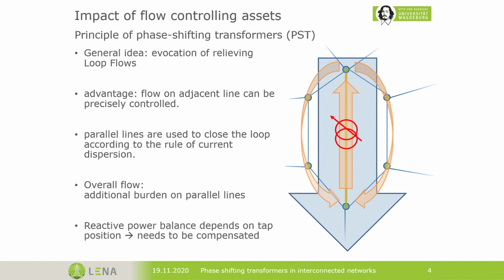All of these lines are therefore utilized from north to south direction. Let's imagine the line in the central part of this picture is overloaded. Then we want to remedy this congestion using a PST, which means we will install a PST in a line to this line. So a series PST. And this PST can be controlled in such a way that it causes a circular flow that is in the opposite direction on this line. And as I said, it's a circular flow.